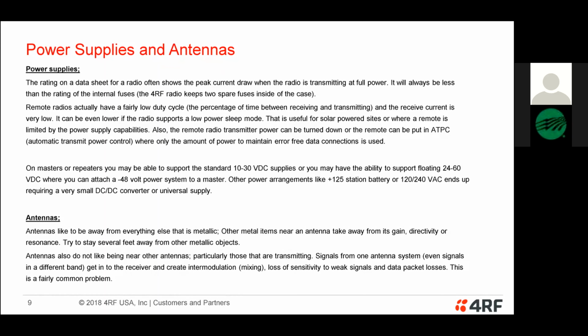I know particularly with that large IOU to the north of you, we were going in and just putting in a little radio that drew 150 or 200 milliamps, and they were replacing station batteries. They tied the entire station battery replacement into the SCADA project, which was probably a good way to get the station batteries replaced, but man, did it drive up the cost and really push out the deployment time to get that done.